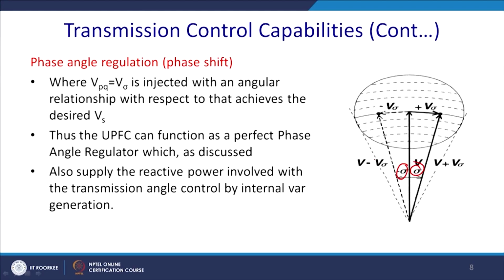The injected series compensation voltage can be kept constant if desired, independent of the line current variation, or can be varied in proportion to the line current. This is the line impedance. Now phase angle regulation: it will change sigma and keep the magnitude the same, where VPQ equal to V sigma is injected with an angle relationship with respect to the line voltage that achieves the desired Vs. Thus, UPFC can function as a perfect phase angle regulator, as discussed here.